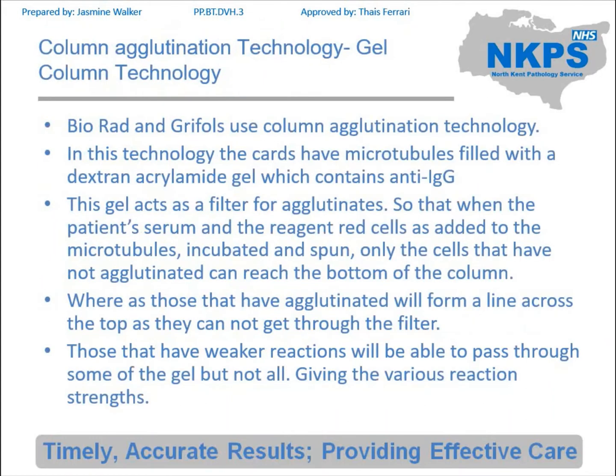We're going to start off with column agglutination technology and specifically gel column agglutination technology. Currently in the hospitals we are both using gel column agglutination technology. In this technology you get a card which will be specific to what test you're doing. So if you're doing ABO grouping then you will get a card which has reagents for ABO — it'll have the antiserum in the card and then it will add in a reagent with red cells on it. This is because generally the stability of the red cells is not good enough to keep it within the card.